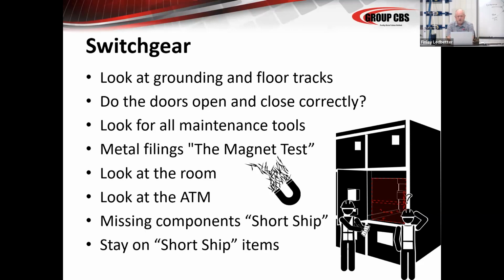I've seen indoor gear accidentally applied outdoor, and if we hadn't caught it, it would have been outdoor. I've seen dry type transformers and NEMA 1 enclosures placed outdoors because someone just made a mistake. In acceptance testing, these sorts of things have to be picked up by the professional. Always look for missing components and short ship items, and then make sure that the users or the owners stay on those short ship lists and make sure they all come.